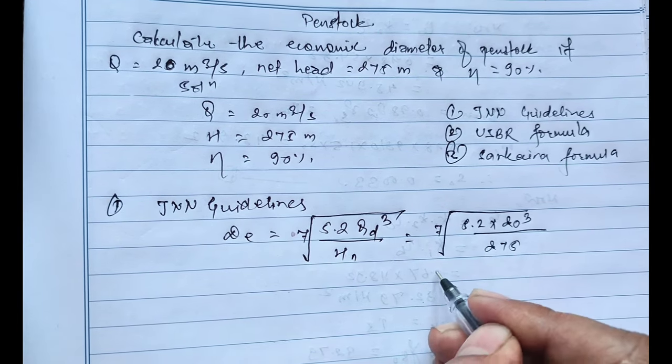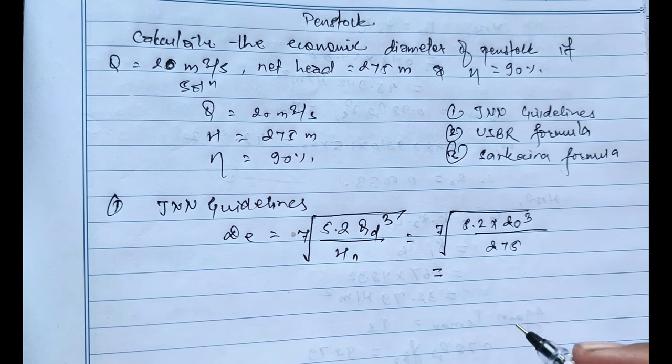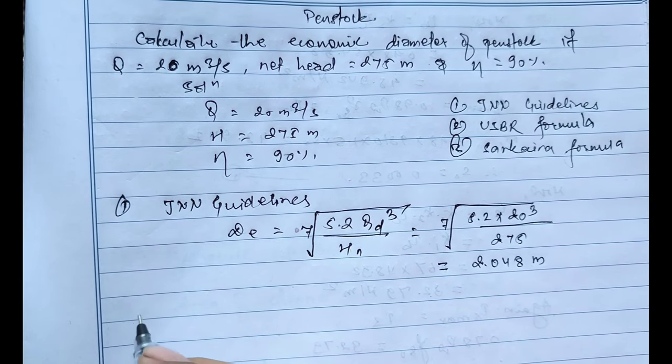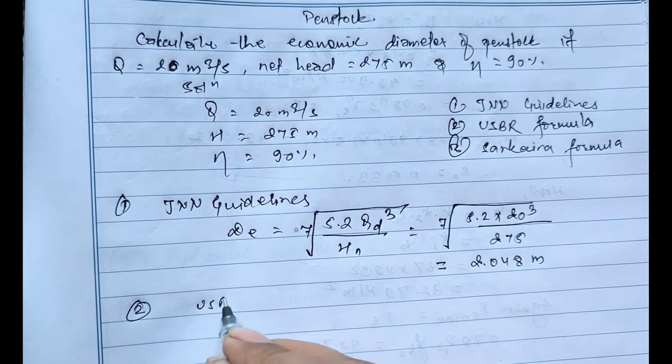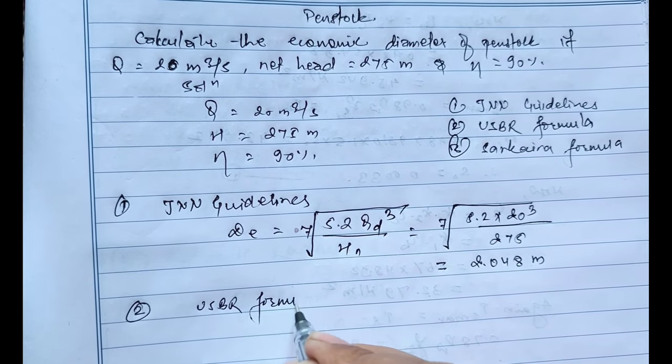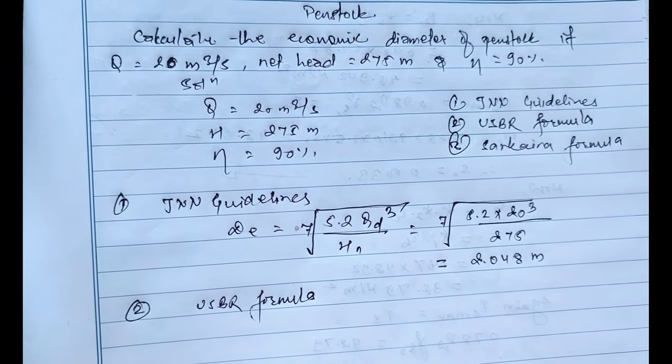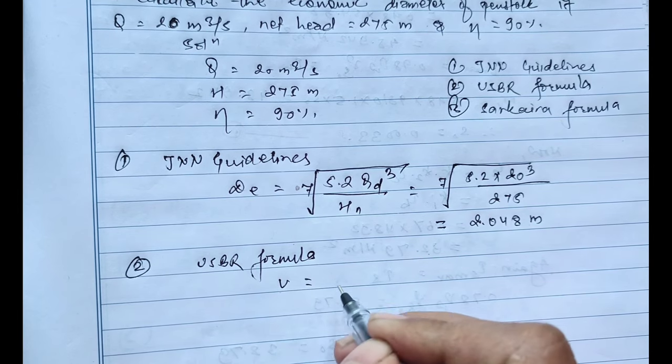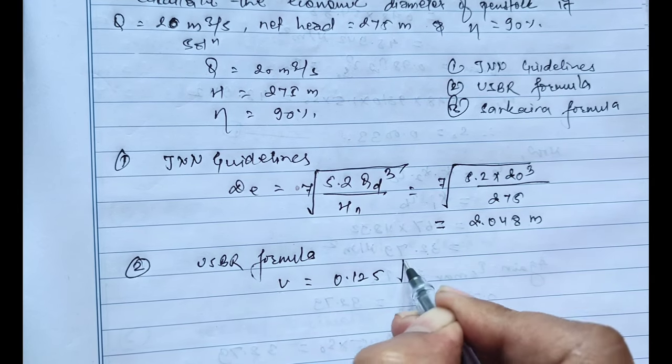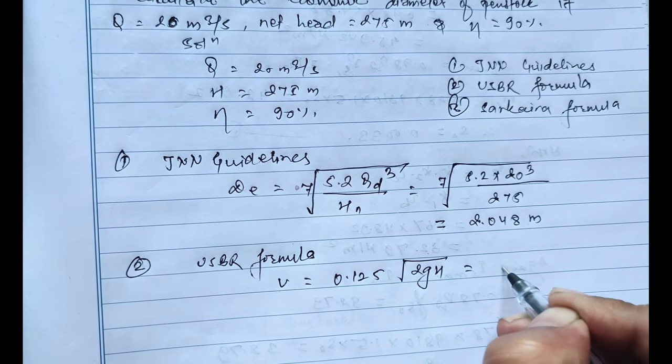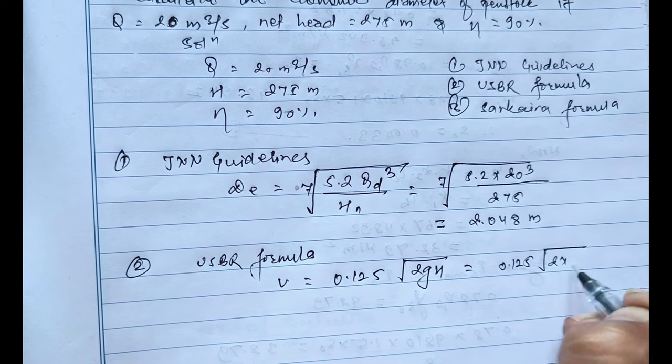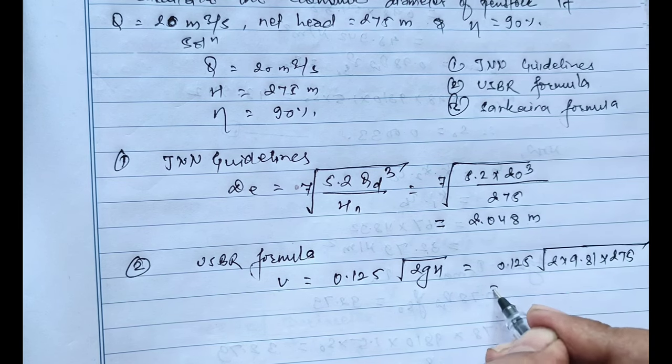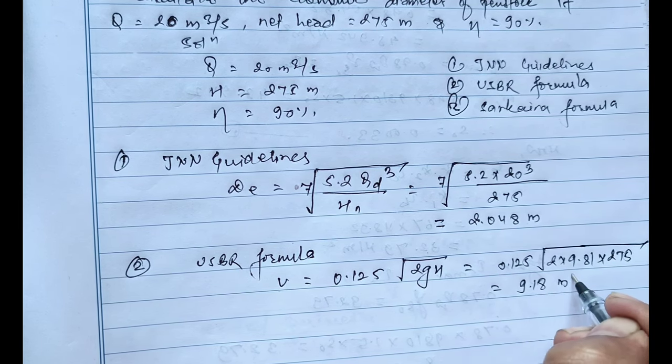Now using the USBR formula, the economic diameter can be found using first V equals 0.125 root over 2gH equals 0.125 root over 2 into 9.81 and the head is 275. On calculating this, the value will be 9.18 meter per second.